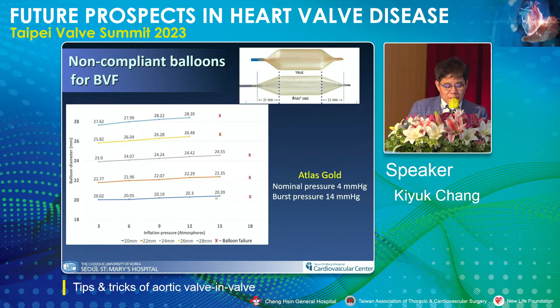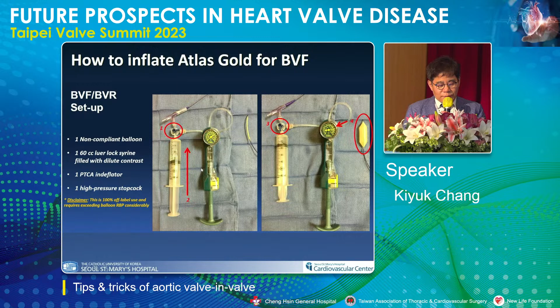So this is the initial setup for the high pressure balloon. You need a large syringe, an indeflator, and a high pressure stopcock. At the time of balloon inflation, initially you have to rapidly inflate with the syringe to inflate the balloon, and then turn the stopcock, so the indeflator increases the pressure to a certain degree. This is the usual setup for a high pressure balloon at the time of valve fracture.